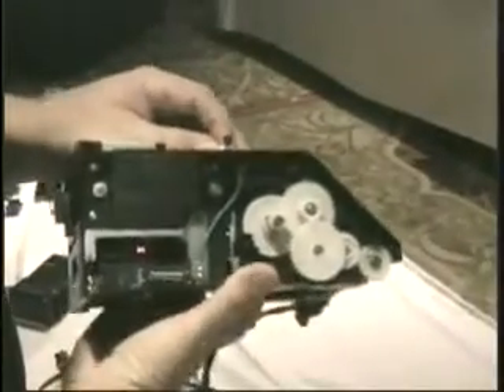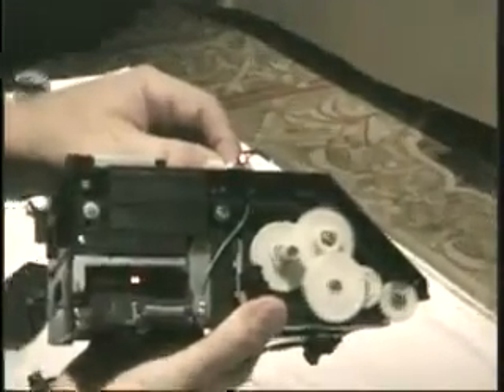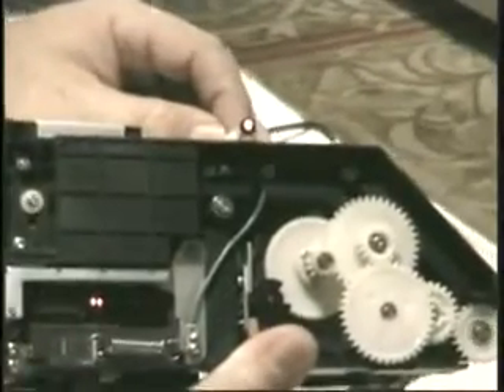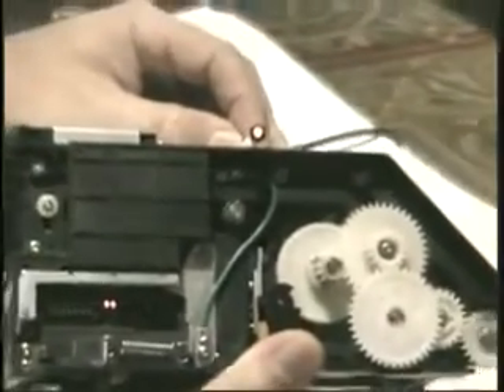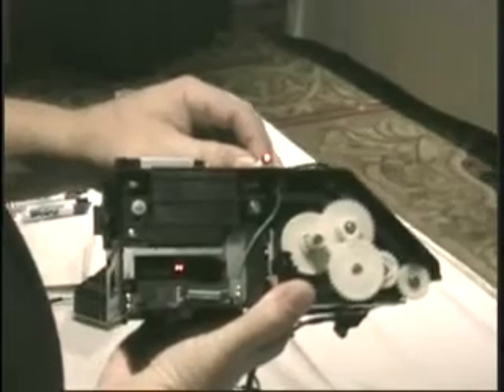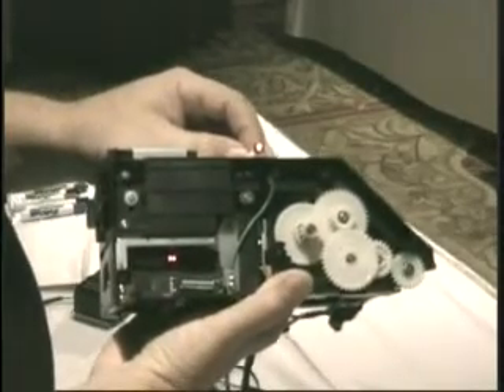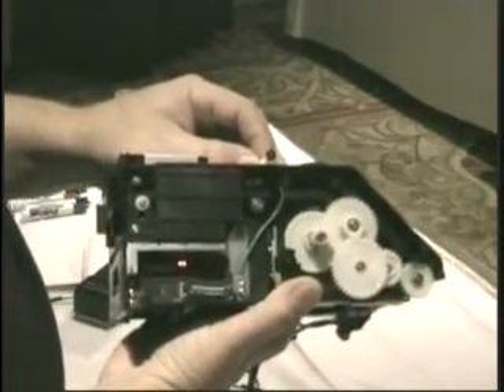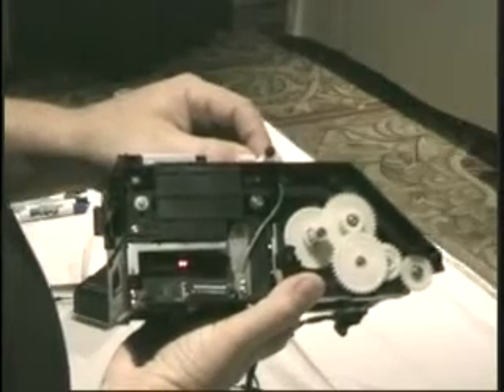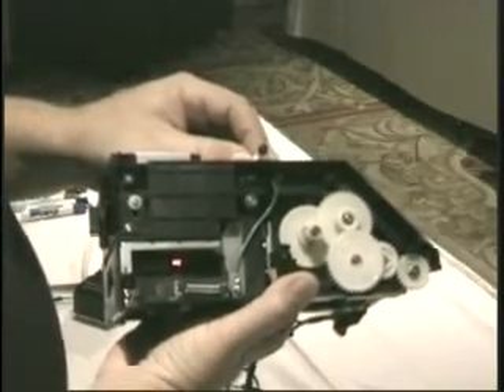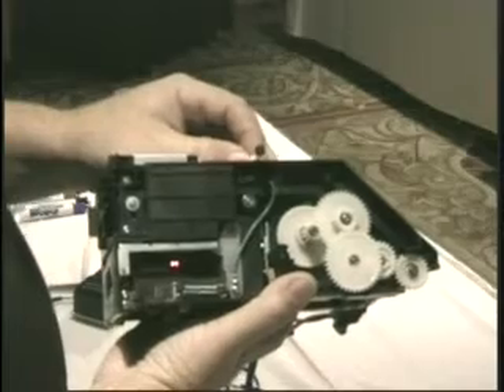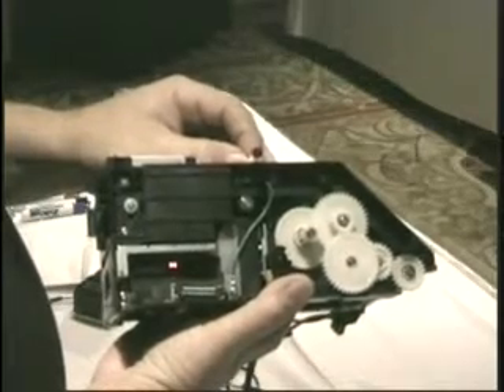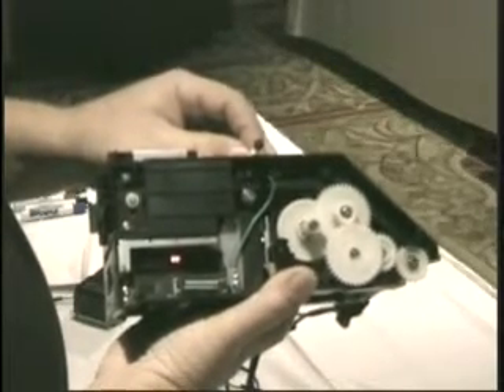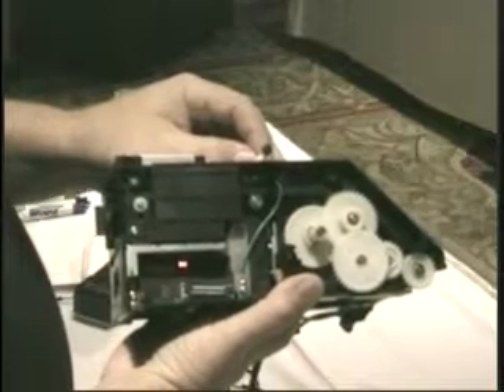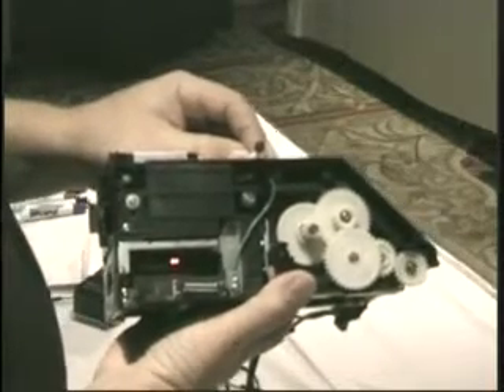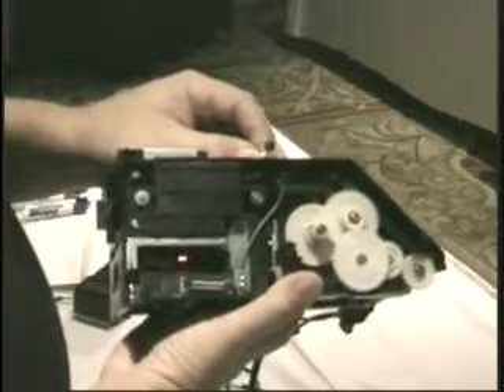If the test light comes on, it means the motor's either running too fast or too slow. I've never seen one run too fast. It's possible, I suppose. I can't imagine how. I can't imagine how either, but anything's possible. If you have an encoder, we had a thing once, there was one shipment of encoders, it was like 300 encoders, I think they caught it at the factory, where it had little pinholes in them from the plastic injection molding, and it was actually reading 2 for every flag that went past it, so that would read fast.